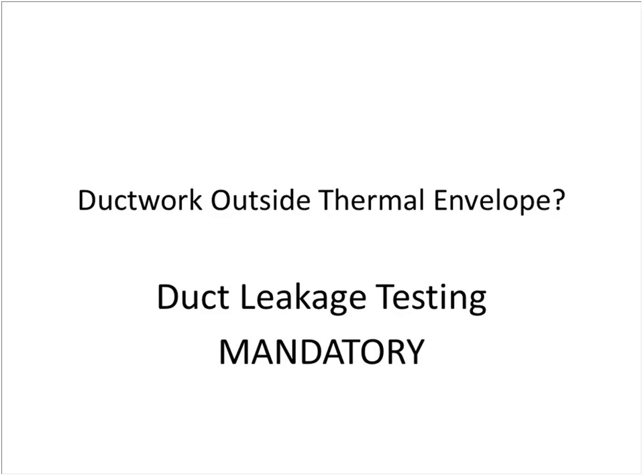There is a requirement in the code, as I was just mentioning, that duct leakage testing is mandatory when the ductwork is outside the thermal envelope. Now, it's considered outside the envelope anytime you don't have full R value between the duct side closest to the ambient or outside the thermal envelope. So if that's a wall in the garage, if you can't get a full R13 with an R5 continuous insulation in that space, or an R20 cavity fill, that's considered outside. So prescriptively, the code then would mandate that your ductwork then be tested.